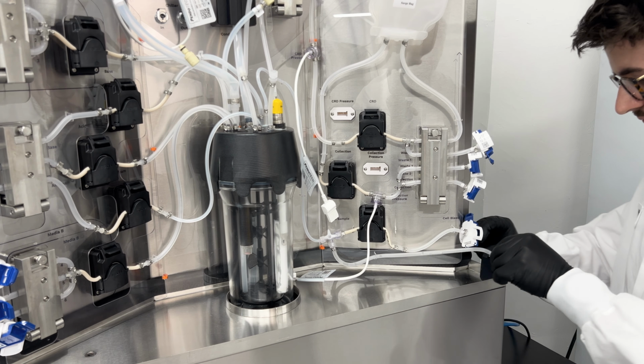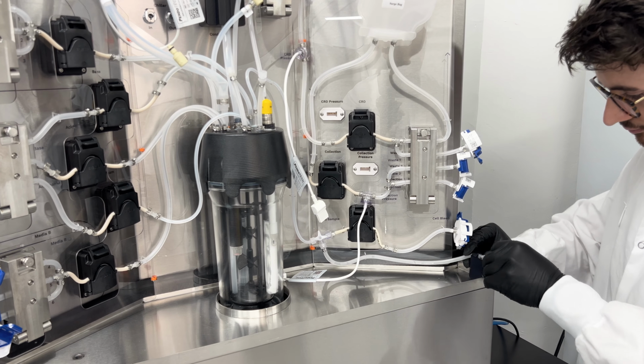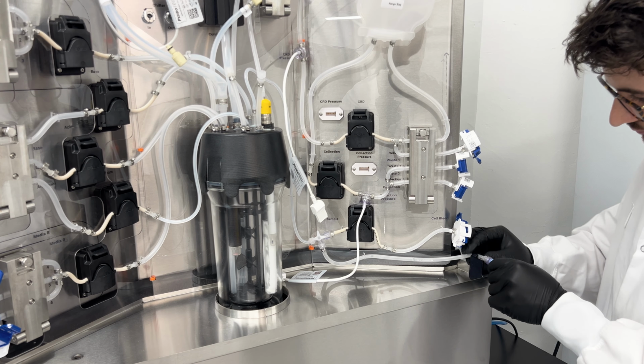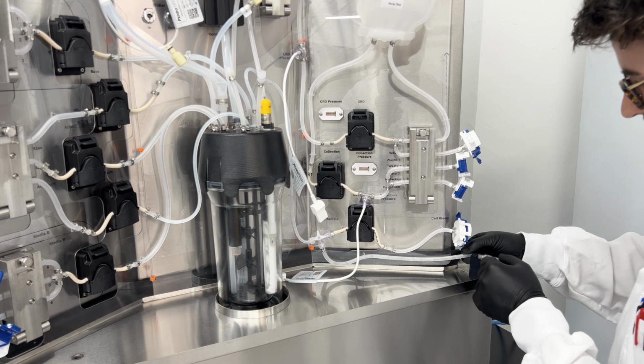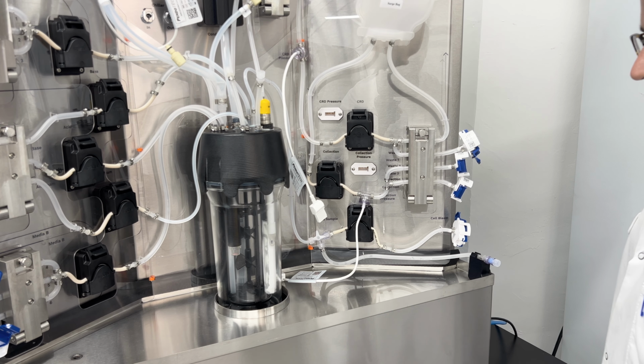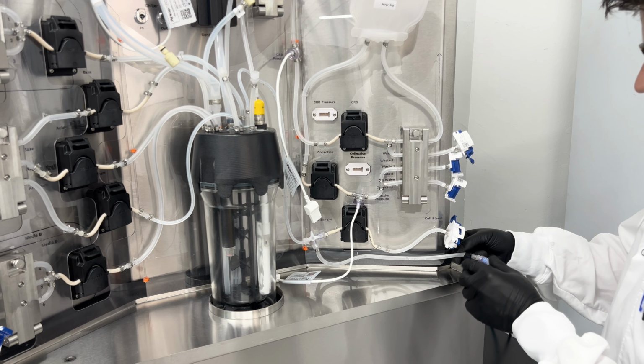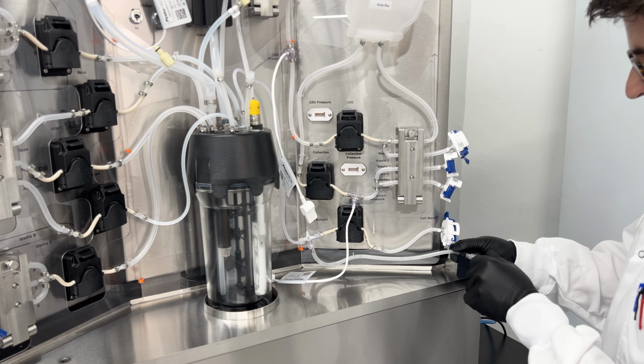After the tubing is properly installed in each pump, we'll clip the sample port onto the mount at the front right corner of the Daisy Petal catch basin by simply pressing the tubing into the clasp at the top of the mount. Push the sample port back so that it sits on top of the concave portion of the mount.